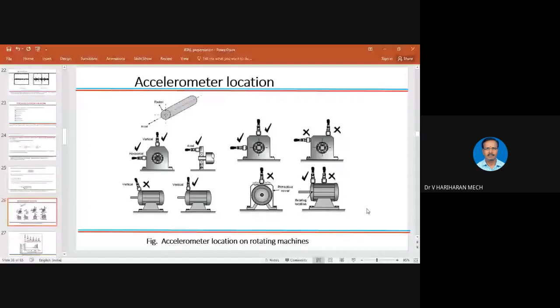So the handheld probe, which is already shown in one of my previous slides, is used to monitor the vibration signals from an induction motor. This first one is the hand probe accelerometer. It is used where the location is not accessible. So for that particular application, we are going to use the handheld probe type of mounting method.